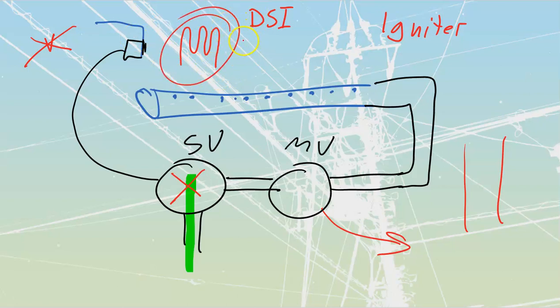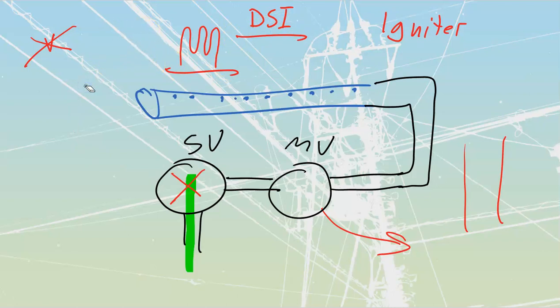So when we want to ignite something with a hot surface igniter, we send a signal to the hot surface igniter. That thing glows white, and once it glows white, we monitor that through the currents inside of these systems. Then it is going to release the gas so that the gas can be ignited by it. Whether we are using this or this, we need some sort of flame-proving device, and a flame-proving device is simply going to be another thermocouple.